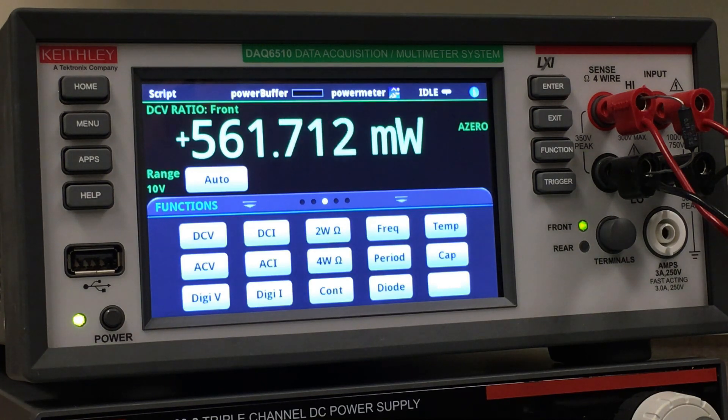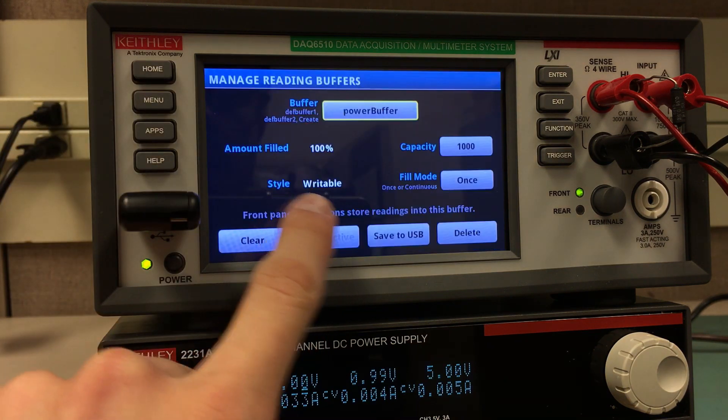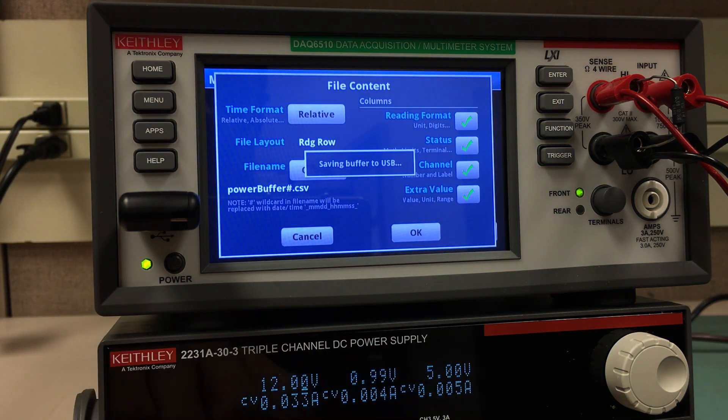This method of measuring power is useful for quickly troubleshooting and for getting a pretty good general idea of how much power a particular branch of your circuit is drawing. Both the power buffer and reading buffer can be exported and saved to a CSV file on a flash drive, like so.